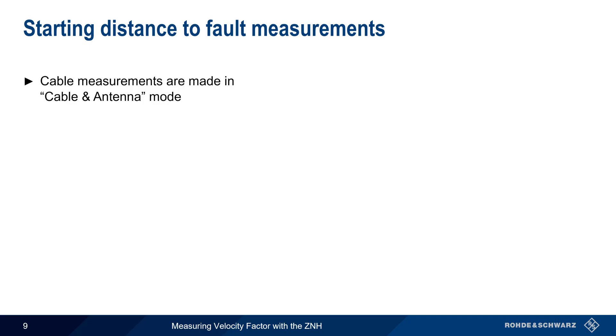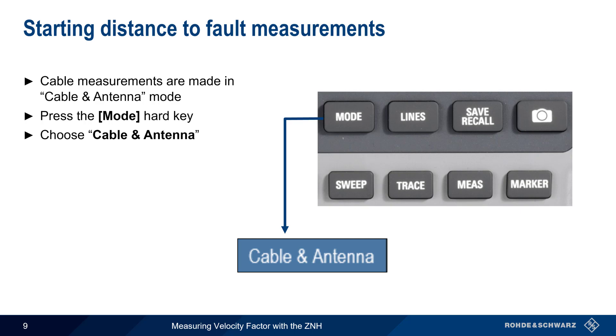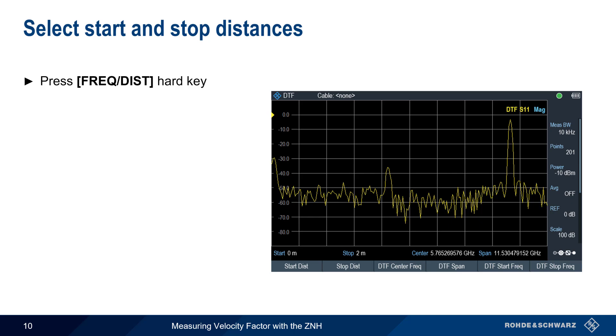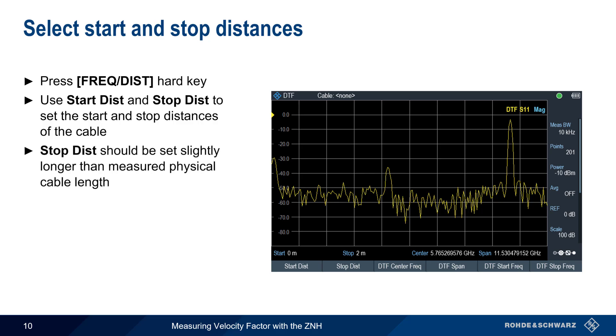On the ZNH, distance-to-fault measurements are made in Cable & Antenna mode. To enter this mode, press the Mode hard key on the front of the ZNH, and then choose Cable & Antenna from the list of available on-screen options. Next, press the Measure hard key and choose Measure Mode DTF. We set the start and stop distance of the cable by pressing the Frequency/Distance hard key, then use Start Distance and Stop Distance. Stop Distance should be set slightly longer than the measured or known physical cable length.